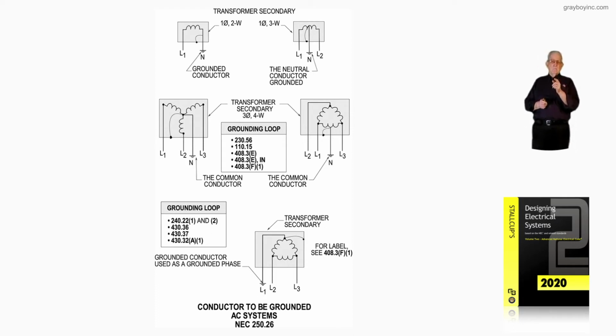Now notice again, to the left at the top, I can pull one hot and one ground. Now it could be a neutral, but it's called a grounded conductor because it's not pulling unbalanced current. It's pulling exactly the same current as your L1. So just one grounded conductor with L1. I couldn't pull two L1s with one grounded conductor and double it in size. That would be prohibited by 250.26.